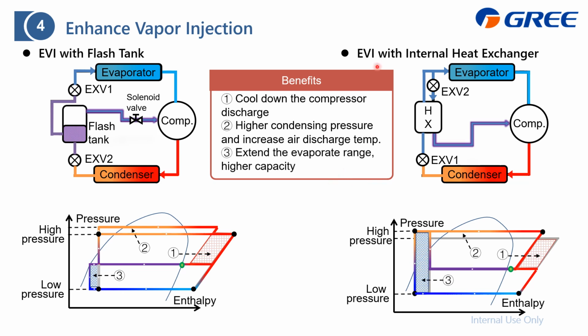And just compared with the flash tank, we have this device to control the injection amount. But with the flash tank, once we fix the solenoid valve, the injection amount is already fixed. It cannot be adjusted. On the other hand, switching this solenoid valve on and off will introduce an impact to the outdoor unit system, which will make the piping vibration not that good. As for the EXV, it is a gradual change which is acceptable by the outdoor unit, or the impact is very small.